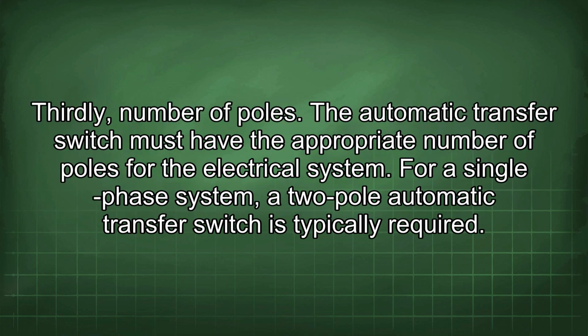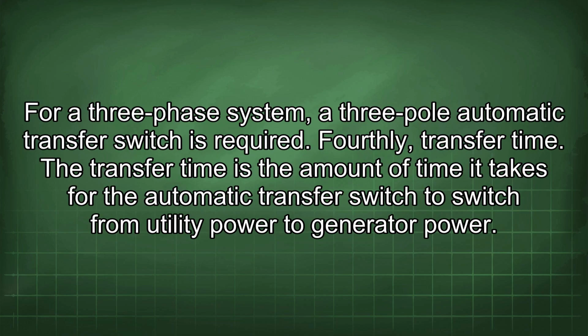Thirdly, number of poles. The automatic transfer switch must have the appropriate number of poles for the electrical system. For a single-phase system, a 2-pole automatic transfer switch is typically required. For a 3-phase system, a 3-pole automatic transfer switch is required. Fourthly, transfer time. The transfer time is the amount of time it takes for the automatic transfer switch to switch from utility power to generator power.